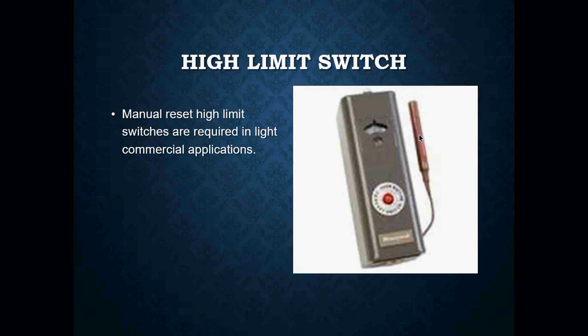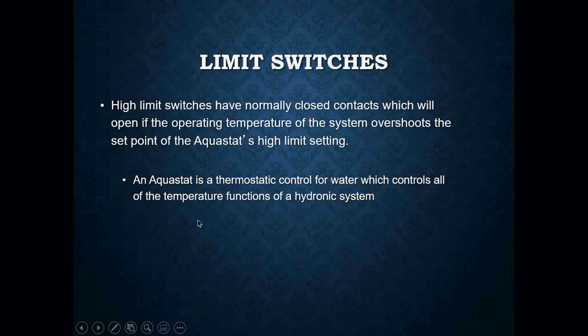This device sits on a pipe or in a well inside the boiler itself and monitors the water temperature of that appliance. If there is an issue where we get too high a temperature, this little red button will pop out and open the contacts, which will shut off your burner. The only way it can be turned back on is if somebody manually pushes that button back in to close the contact again. High limit switches have normally closed contacts which will open if the operating temperature overshoots the set point.